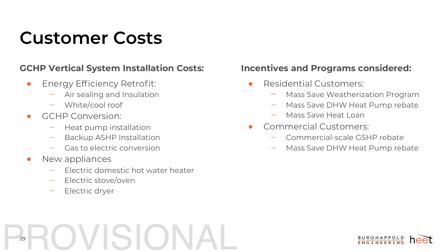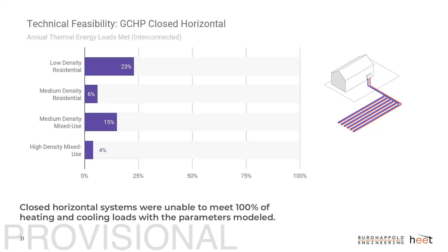At the end of the day, the closed horizontal systems didn't perform that well, partially because there isn't much room in the street right of way. It was difficult to size those to meet 100% of heating and cooling loads, though this isn't to say it's impossible. We purposefully didn't consider installations in a parking lot, park, or private yard. We focused on the right of way, and to the extent possible, on that 2-foot strip of natural gas utility right of way. You could say this is a very conservative case.